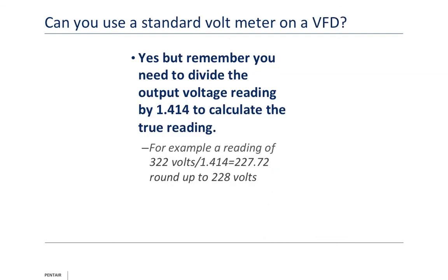Now, can you use a standard meter for a VFD? I get this question not so much anymore, because an RMS, or root mean square, type of meter or a low pass filter meter are now much more common. But probably about 5-6 years ago, we got this call about once a week: Oh my goodness, I'm reading 322 volts on my VFD output. I'm going to burn up my motor.